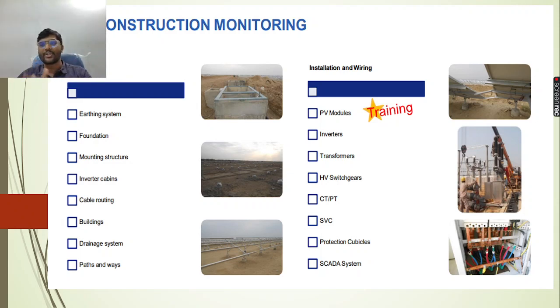Next thing is the installation wiring. We need to make sure the PV modules have been installed and wired properly, and also check that the inverter has been installed at the right location. If you're going for a high voltage installation, make sure the transformers have been installed properly. Then we need to ensure the high voltage switchgears are installed properly, and most importantly, for monitoring purposes in the high voltage systems, we might be using current transformers or potential transformers. We need to make sure they have arrived and been installed as per the design. Then we need to do the protection cubicles. And at last, for the energy monitoring, we can use the SCADA systems also.